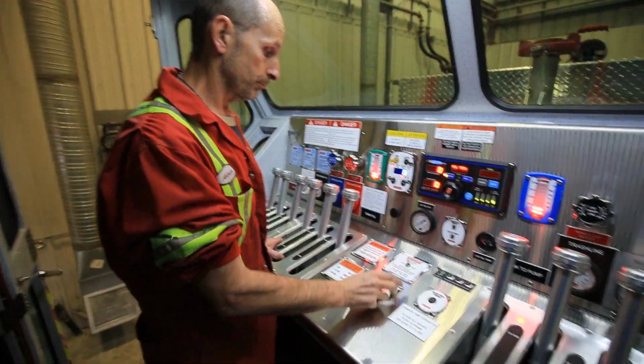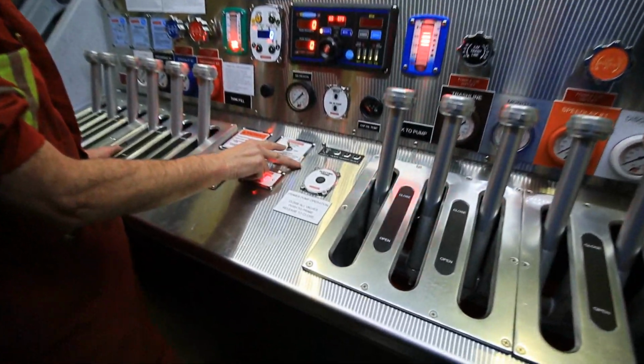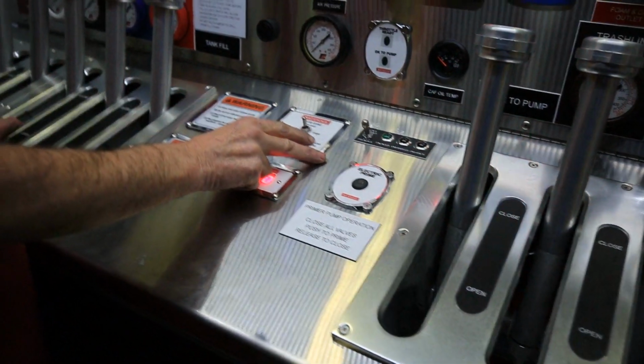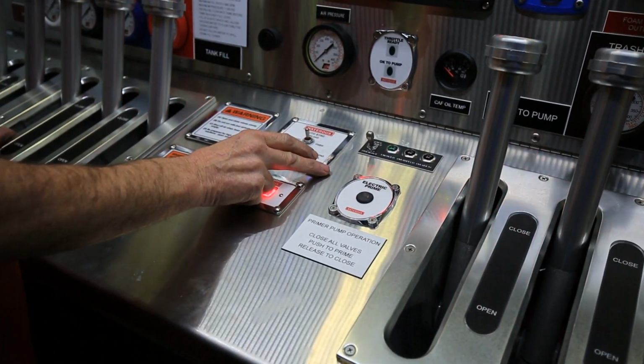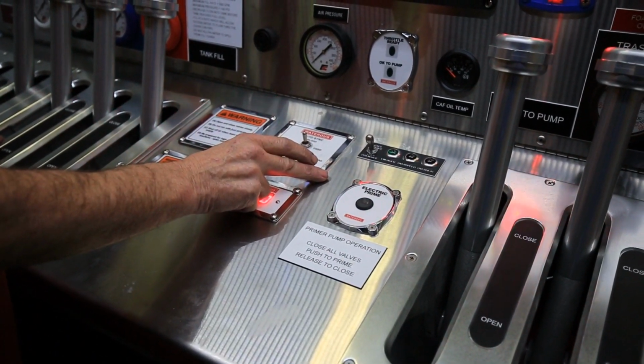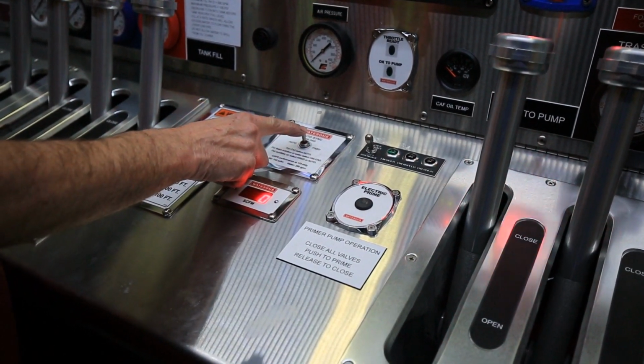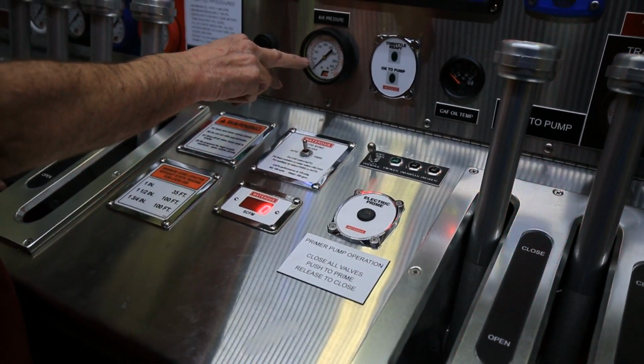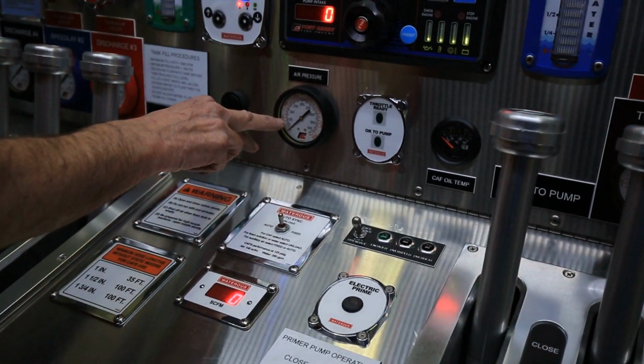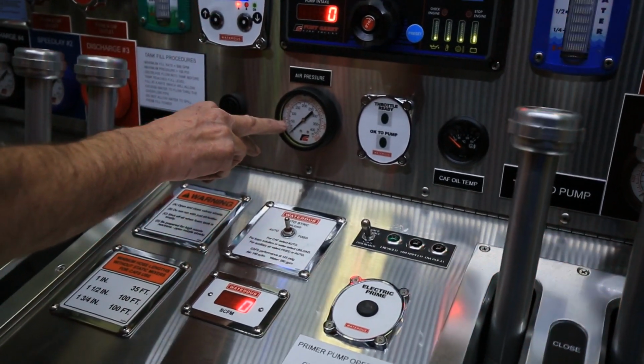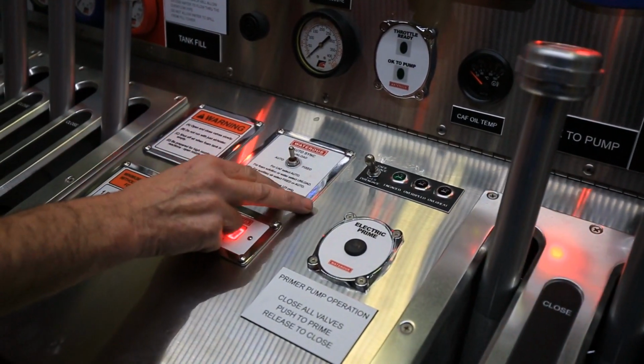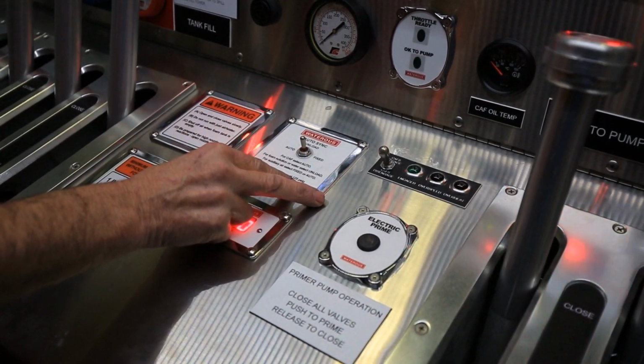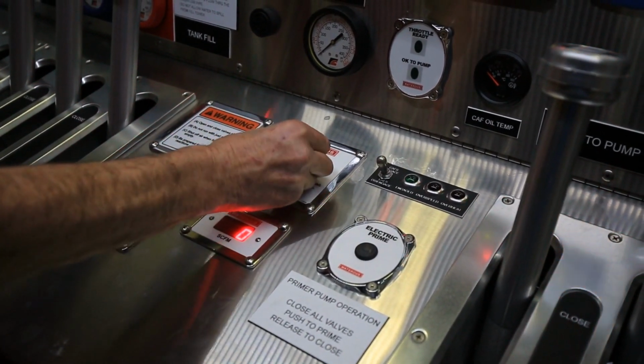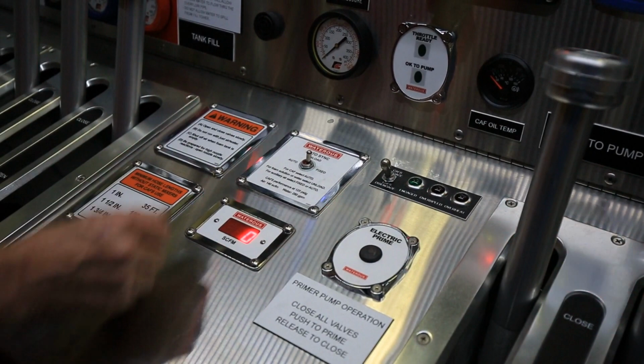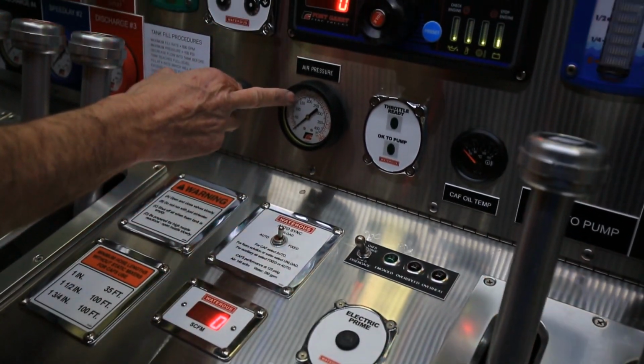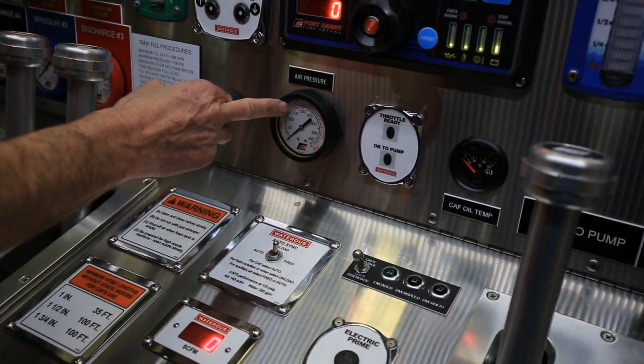The second switch is the CAFS load, unload and fixed switch. The CAFS should always be started in the unload position, and once the CAFS is started, the pressure on the gauge will be approximately 40 psi. If using the CAFS to supply air to power tools, the fixed position can be used, which will set a preset pressure on the gauge to 150 psi.